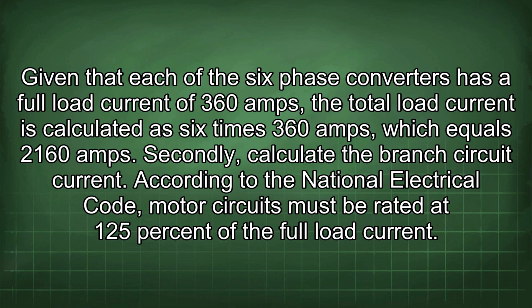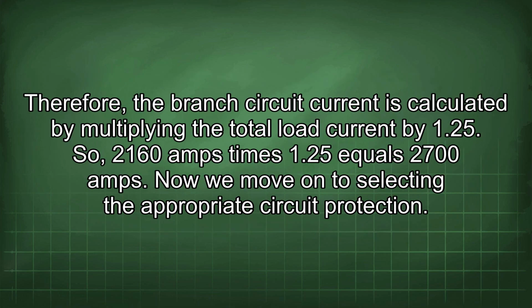Secondly, calculate the branch circuit current. According to the National Electrical Code, motor circuits must be rated at 125% of the full load current. Therefore, the branch circuit current is calculated by multiplying the total load current by 1.25. So 2160 amps times 1.25 equals 2700 amps.